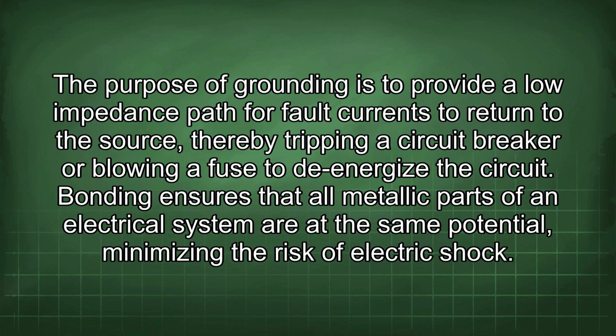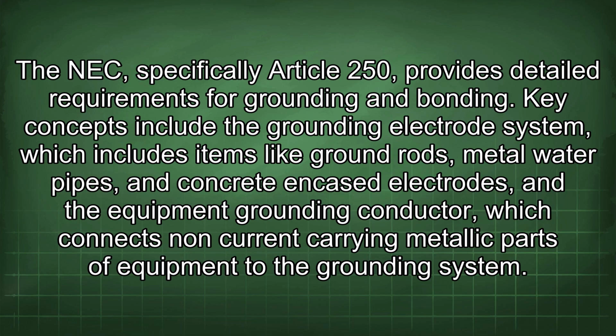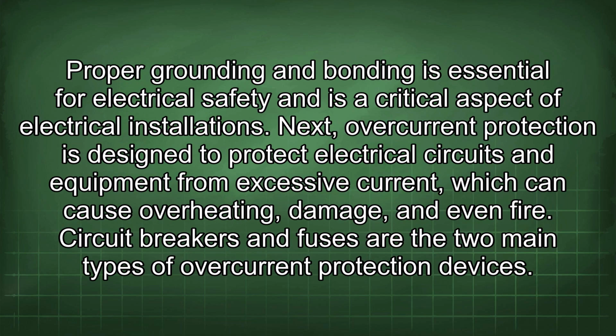The purpose of grounding is to provide a low impedance path for fault currents to return to the source, thereby tripping a circuit breaker or blowing a fuse to de-energize the circuit. Bonding ensures that all metallic parts of an electrical system are at the same potential, minimizing the risk of electric shock. The NEC, specifically Article 250, provides detailed requirements for grounding and bonding. Key concepts include the grounding electrode system, which includes items like ground rods, metal water pipes, and concrete encased electrodes, and the equipment grounding conductor, which connects non-current carrying metallic parts of equipment to the grounding system. Proper grounding and bonding is essential for electrical safety and is a critical aspect of electrical installations.